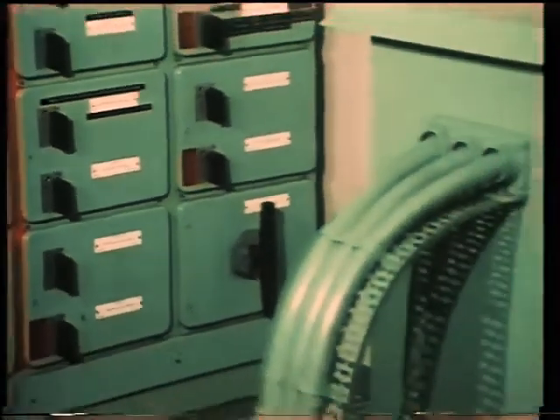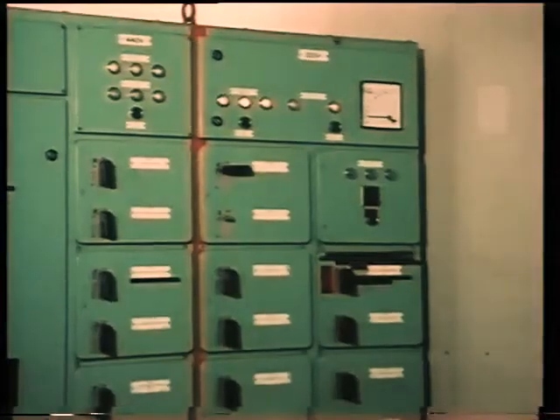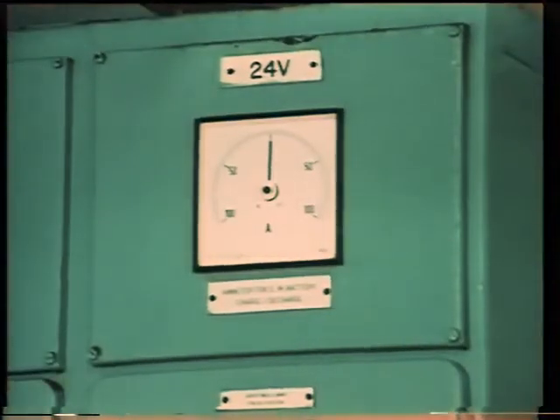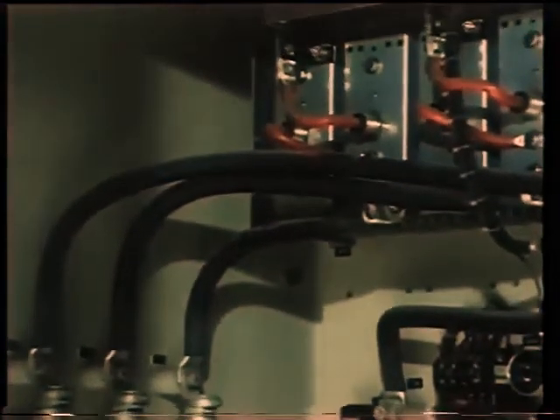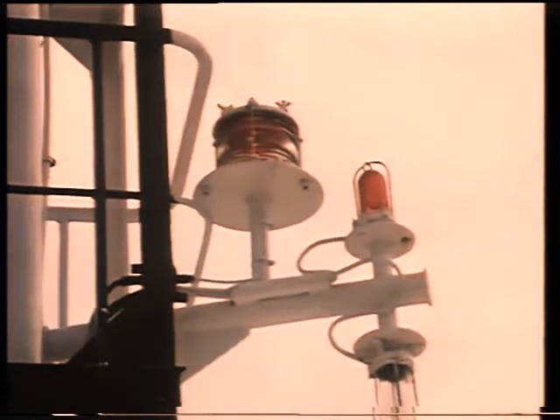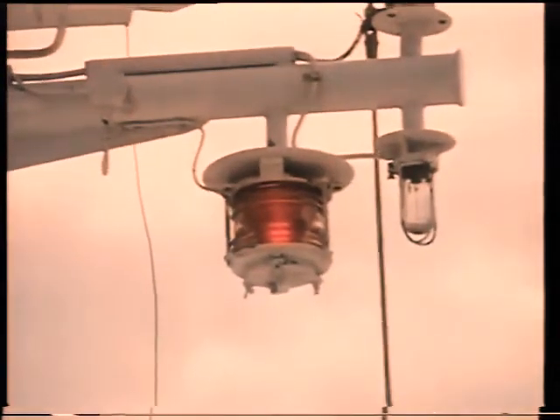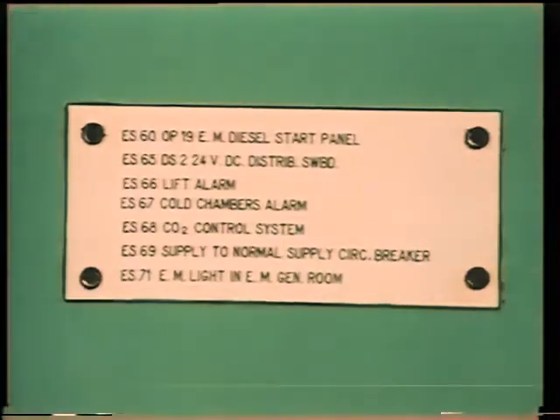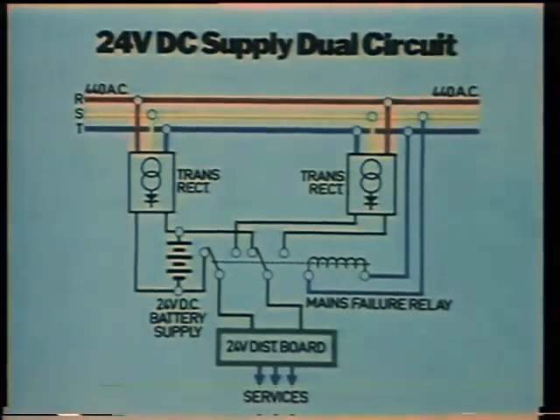One of the feeder circuits supplies a bank of transformers, which reduces the voltage level to 220 volts, or in some cases, 110 volts for lighting and other consumer units. Another circuit provides typically 24-volt DC supply through a transformer rectifier system. This supply provides emergency power for emergency lighting, the not-under-command signal lights, certain navigation aids, and the communication and alarm systems on board ship, in parallel with the emergency batteries. On a separate feeder circuit, a battery charger keeps the emergency batteries on charge during normal conditions.